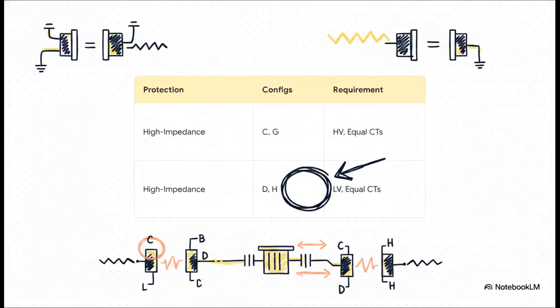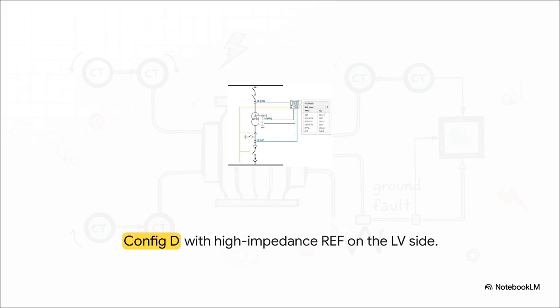Conversely, if you're going the high impedance route, you'll look at configuration C and G for the HV side and configurations D and H for the LV side, and take a close look at the explicit requirement highlighted right there on the screen, equal CTs. Ordering configuration C, D, G, or H for a network with mismatched CT ratios is going to leave you completely unable to commission the protection scheme. It's a dead end.